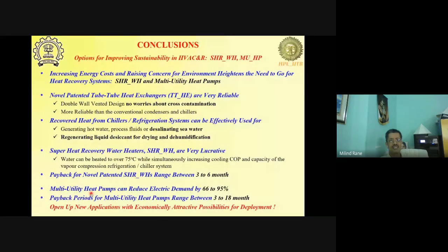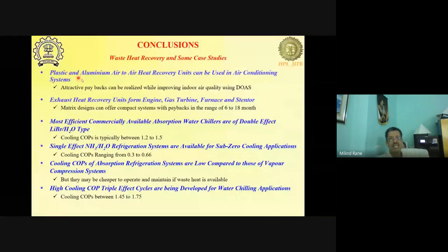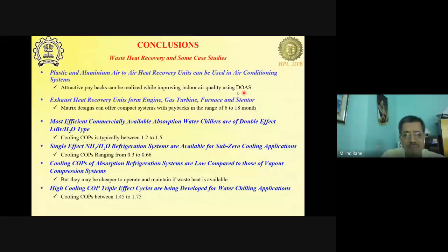Okay, so I think I'll just briefly conclude here. Plastic and aluminum air-to-air heat recovery units can be used in air conditioning systems. Okay, attractive paybacks are possible, and these dedicated outdoor air systems can be very effective. Exhaust heat from gas turbines, engines, furnaces, and so on can be used, and the typical payback would be anywhere between 6 to 18 months. Typically 6 months if you have around a year utilization. You have at least uses for 10 to 12 hours per day. Then we can use lithium bromide water systems, double effect, to club with these recovered heat, or as I said, the latest is liquid desiccant systems that can give you very high COPs.